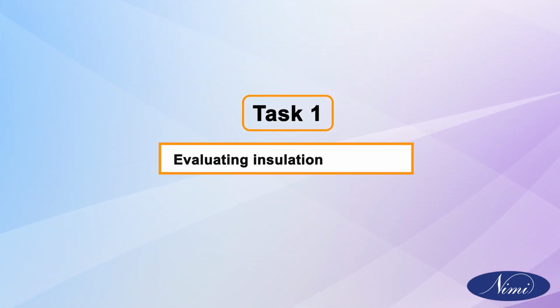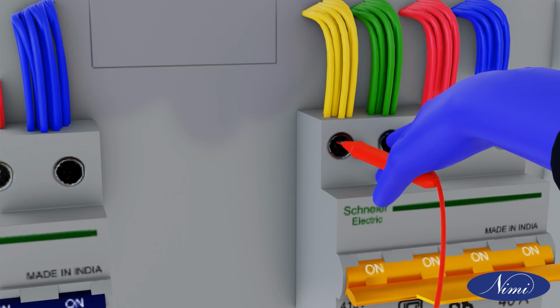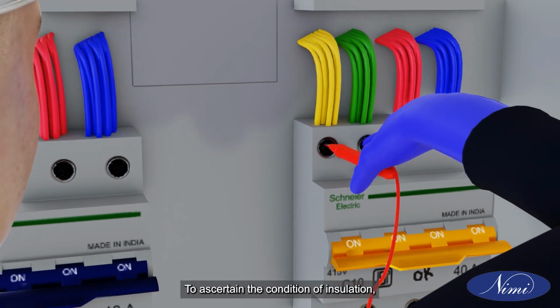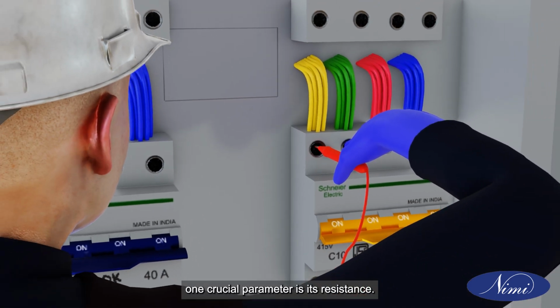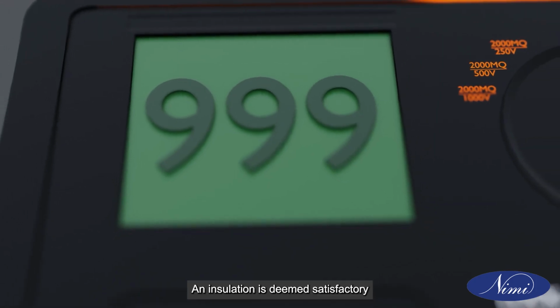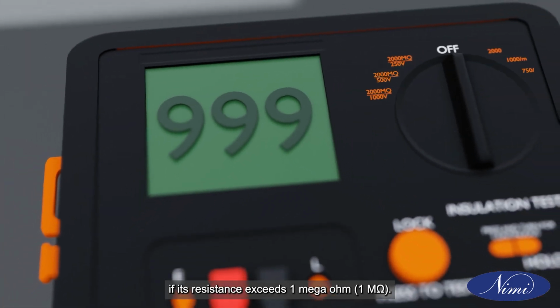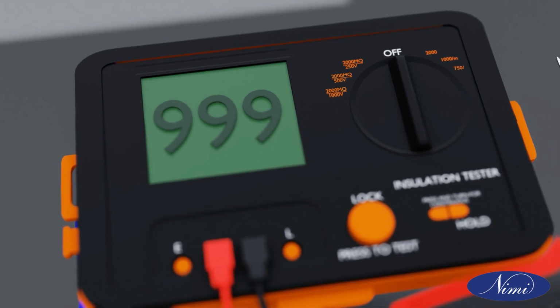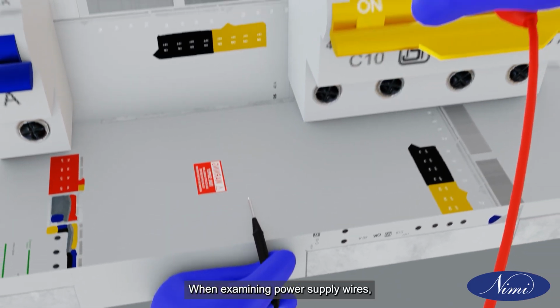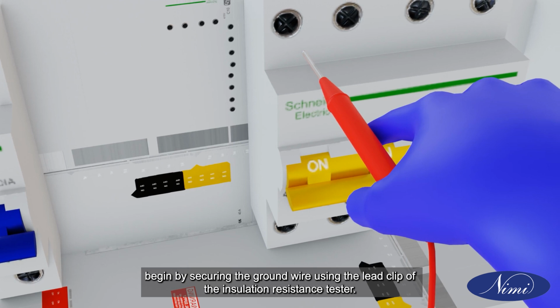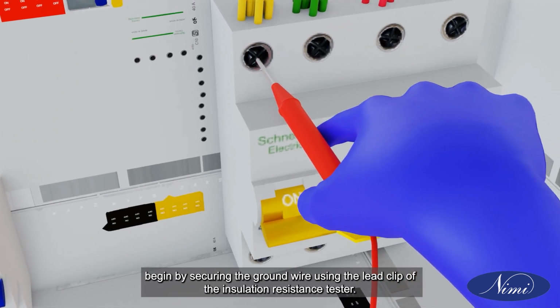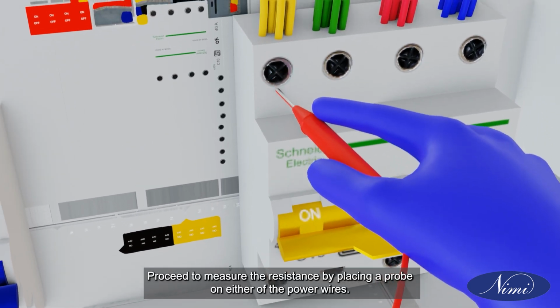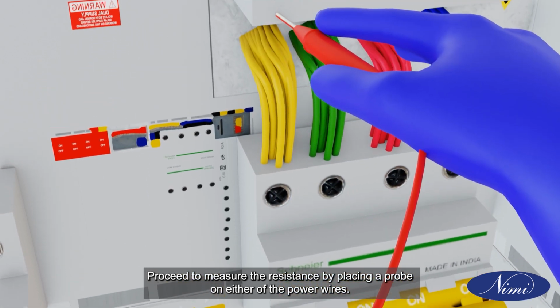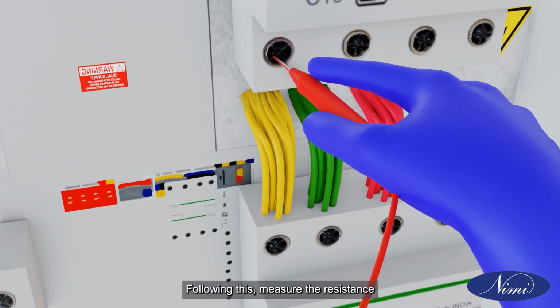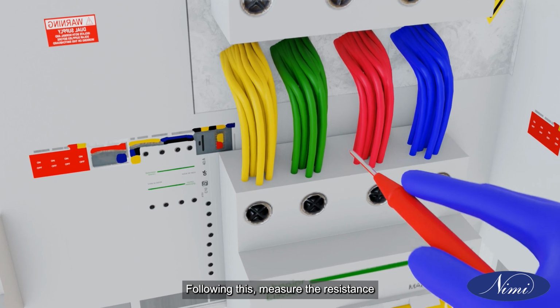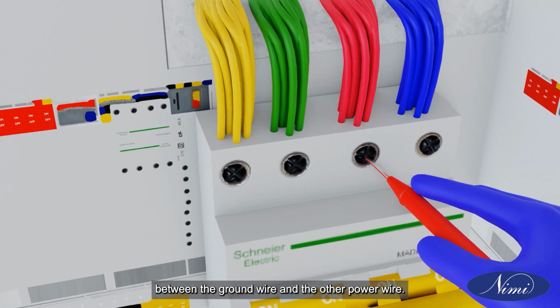Task 1. Evaluating insulation resistance. To ascertain the condition of insulation, one crucial parameter is its resistance. An insulation is deemed satisfactory if its resistance exceeds 1 mega ohm, 1 M. When examining power supply wires, begin by securing the ground wire using the lead clip of the insulation resistance tester. Proceed to measure the resistance by placing a probe on either of the power wires. Following this, measure the resistance between the ground wire and the other power wire.